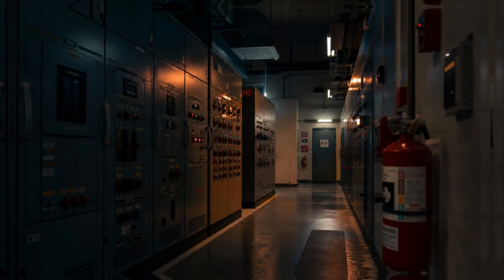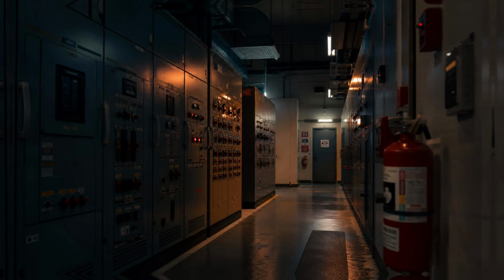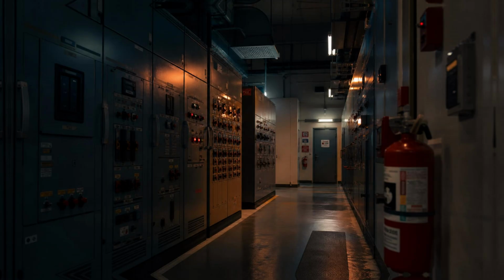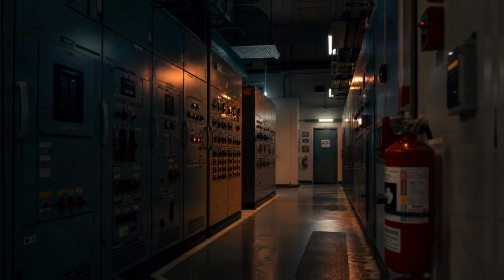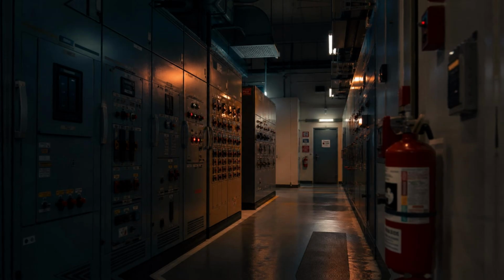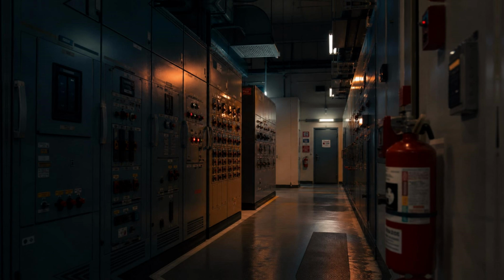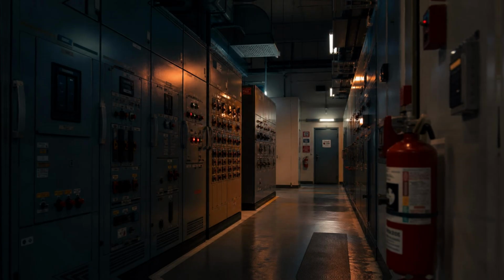The engine starts, comes up to speed, produces its output, and that output simply runs into the generator's own controls and verification systems rather than being transferred to serve the building. No-load exercises verify that the engine starts and runs, but they do not test the full capability of the system because they do not exercise the transfer switch or verify that the generator can sustain real load.